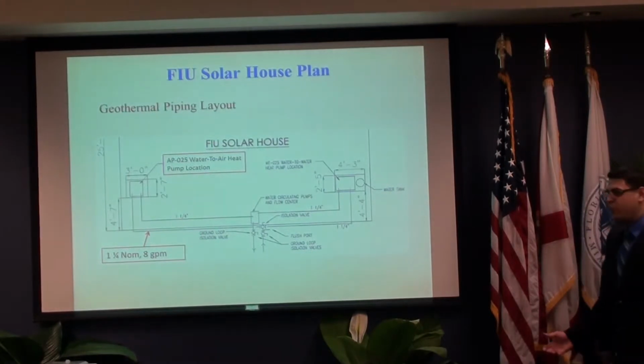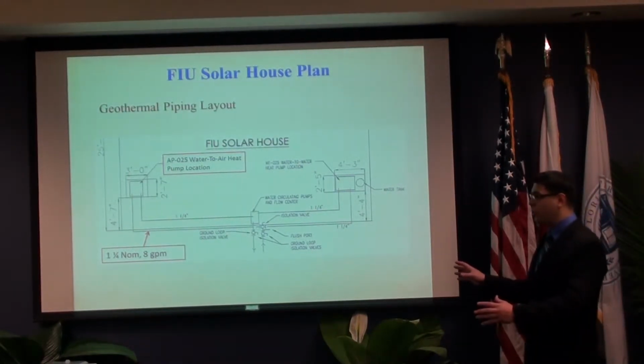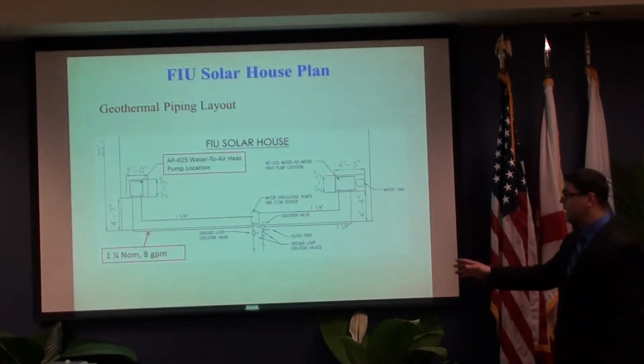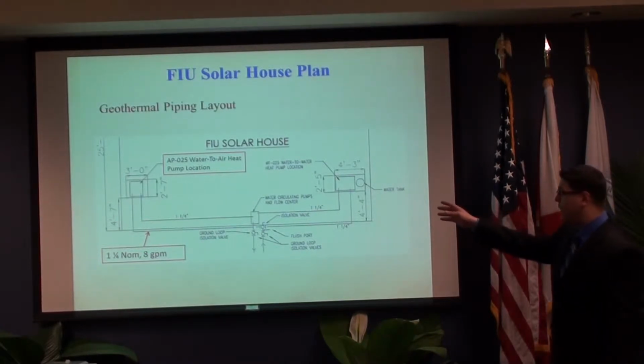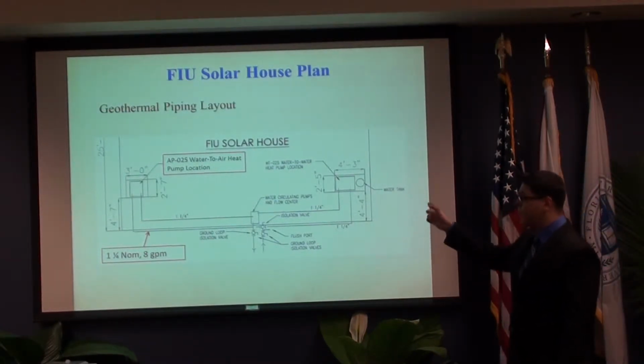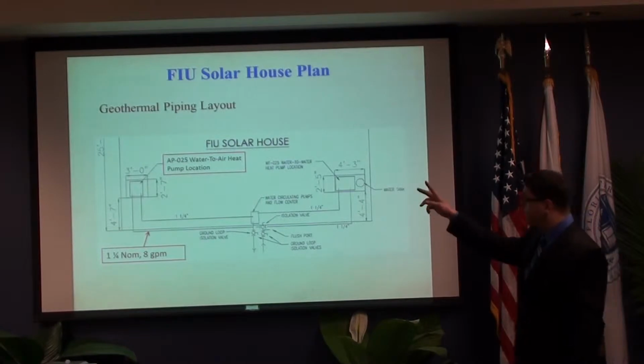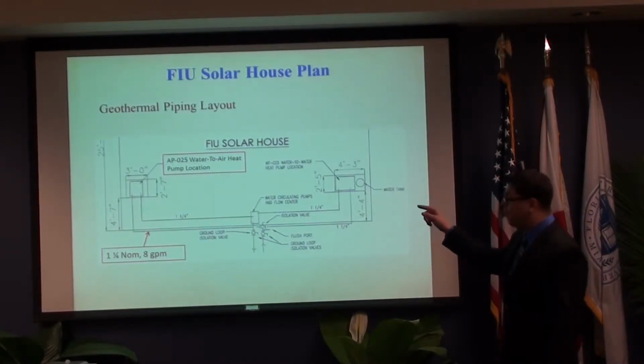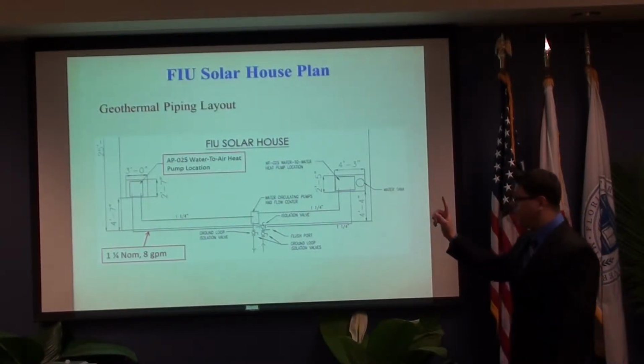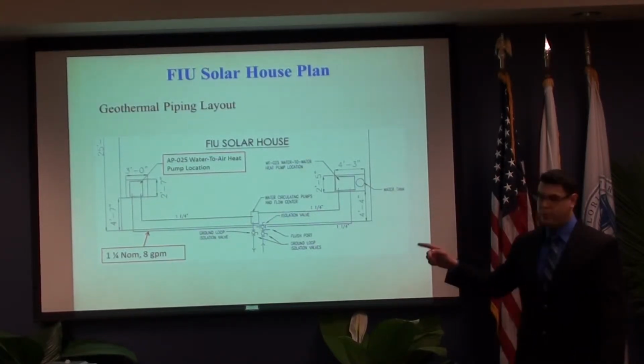Okay, so we started out with one of the FIU solar house plans. This is a close-up of the geothermal piping layout. As you can see in the top left, you have the location of the water-to-air heat pump that's located inside the FIU solar house. And from this close-up, we can determine that the water lines entering and leaving are of a 1 1/4 nominal pipe size with a volumetric flow rate of 8 gallons per minute.